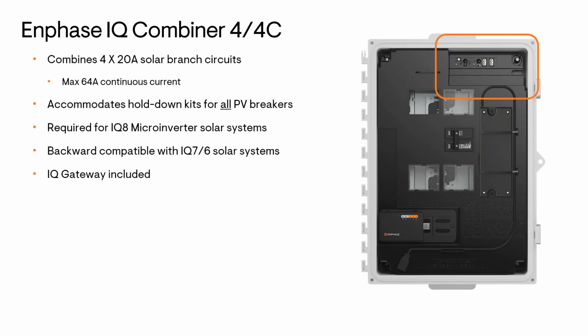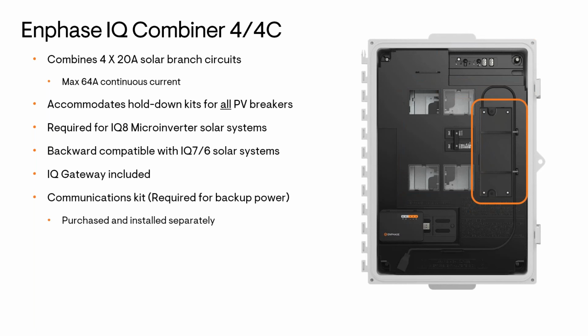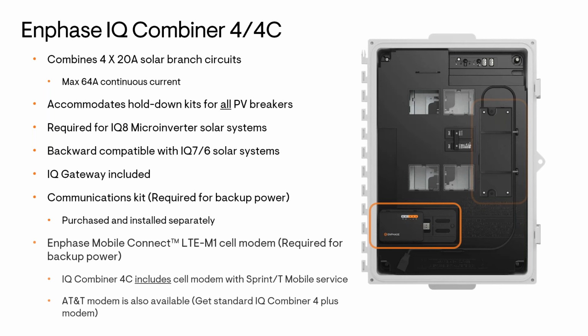I mentioned it has the gateway built into it, and the communications kit must be purchased separately and installed. The communications kit is a wireless communications kit that allows for comms between the components in the backup system, namely the system controller 2 and the batteries. And then lastly, an Enphase cell modem must also be installed.